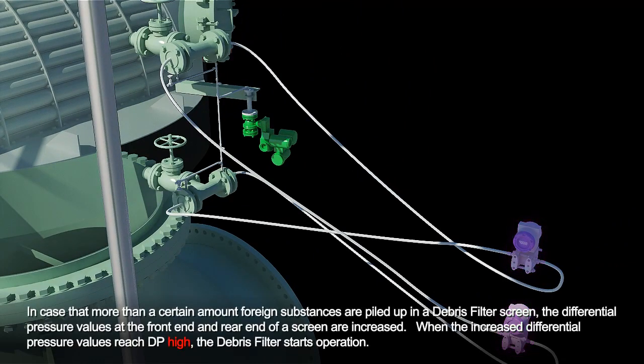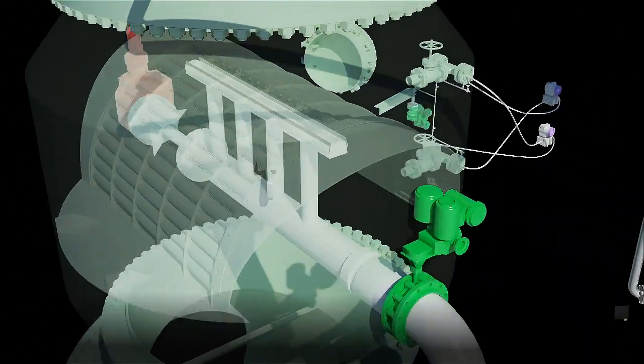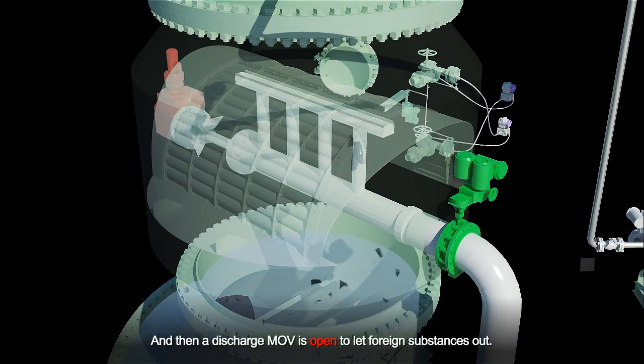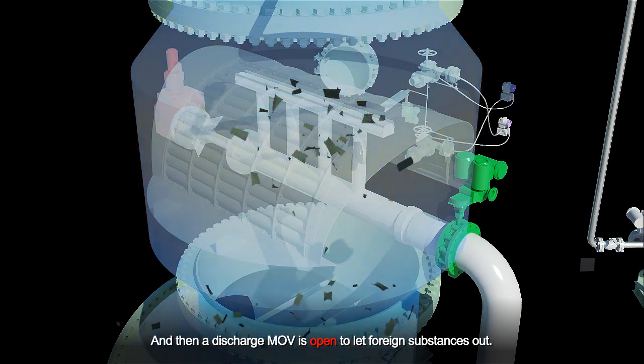In case that more than a certain amount of foreign substances are piled up in a debris filter screen, the differential pressure values at the front end and rear end of a screen are increased. When the increased differential pressure values reach DP high, the debris filter starts operation. And then a discharge MOV is open to let foreign substances out.